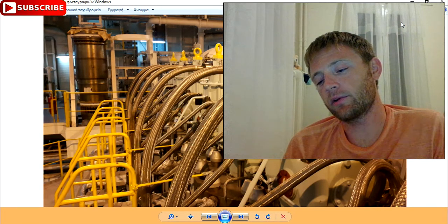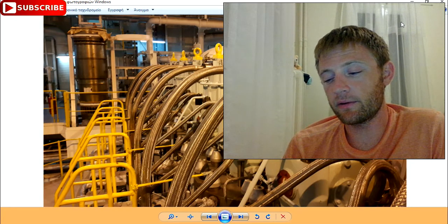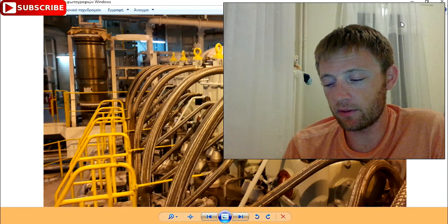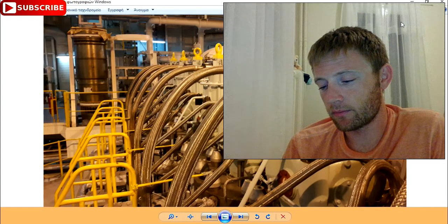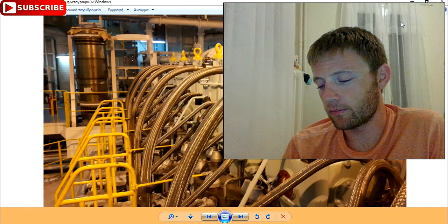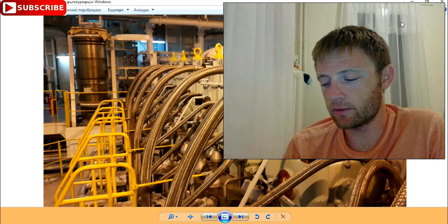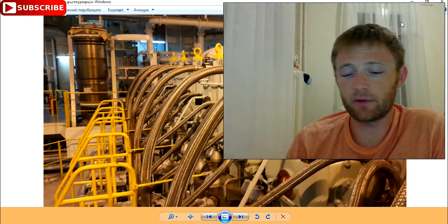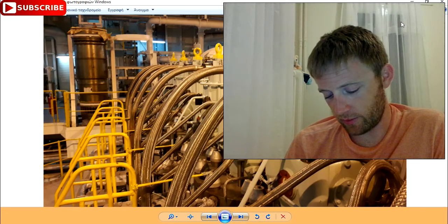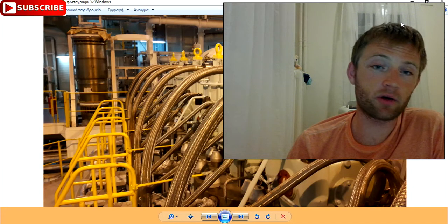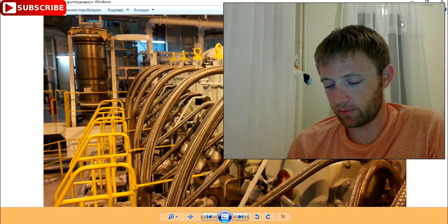Next we will continue to number 28. If there is no increase in pressure in the system, 99% this is a problem with the unloading valve. Okay. And we will find it if we put the other power pack to work, and we will see if the one increases pressure or the other will not increase. Okay. These are very nice notes, which maybe help someone. I will keep them. Maybe in the future I will use them. I don't know, but I will keep them.